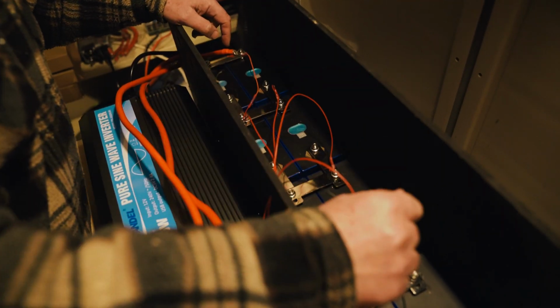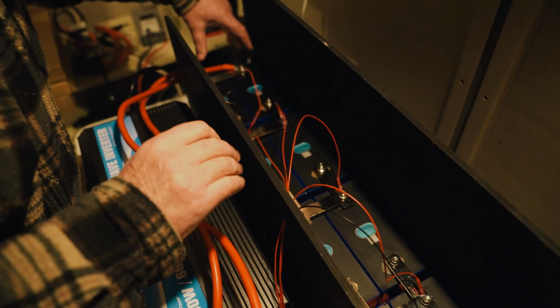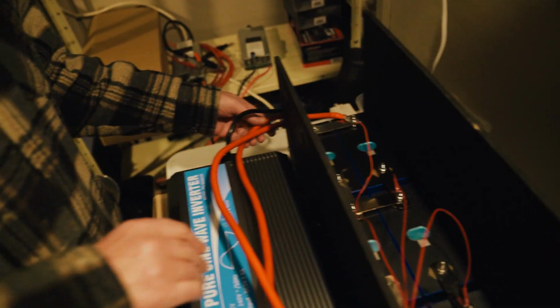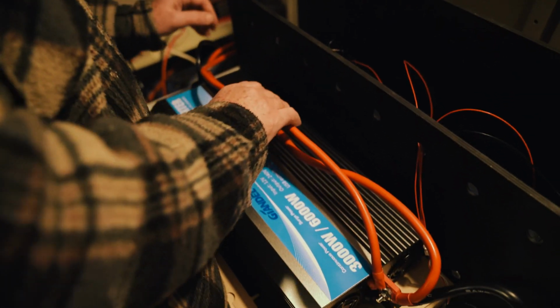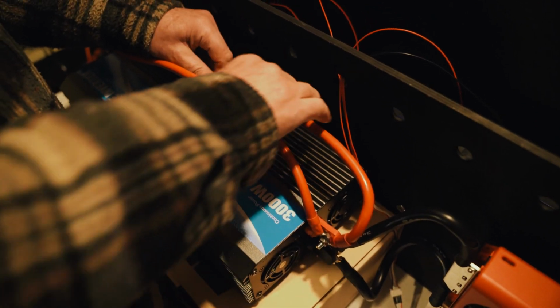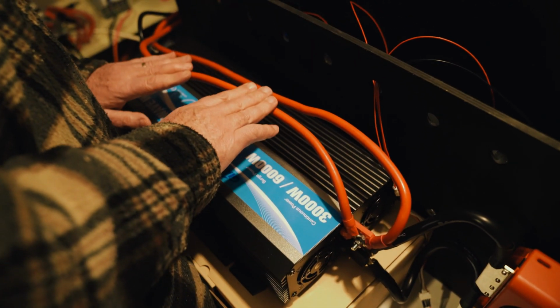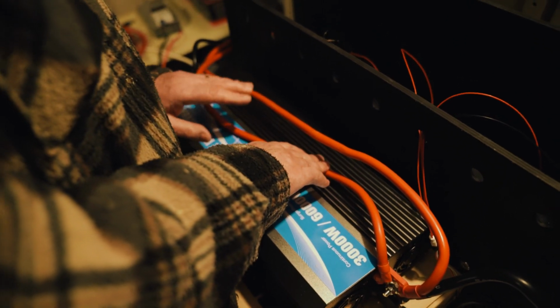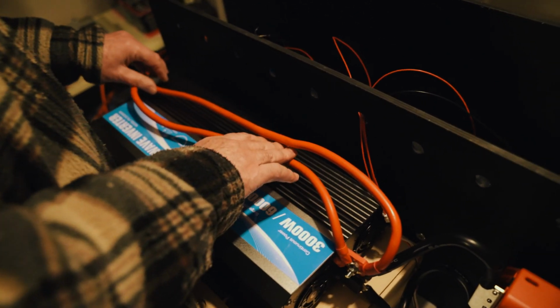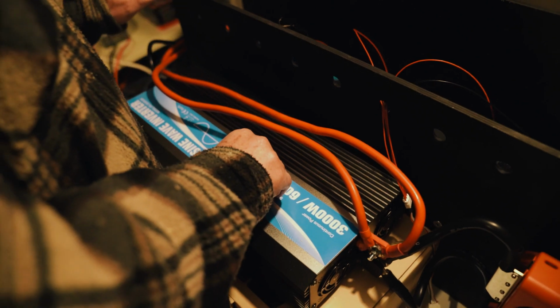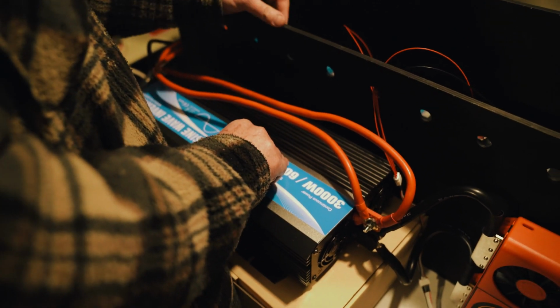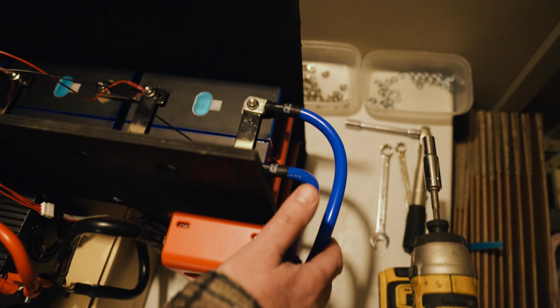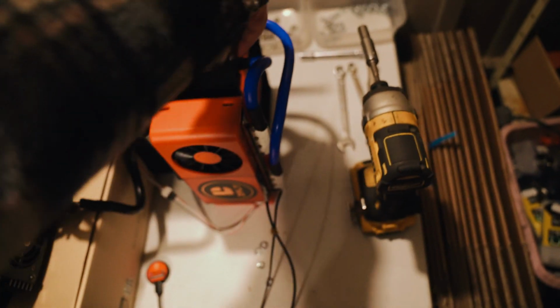This is just so we can monitor temperature across all of the terminals on the cells and the BMS and everything. So we've got the cells all connected up as they need to be, and we've got two 25mm squared cables running to the inverter. We're using 25mm squared for the purpose of this video, which is ample for the total capacity that this inverter and BMS can cope with, so 300 amps. But when it comes to actually building the battery out finally, we're going to put 35mm squared cable there just because we can. On the BMS, it has 4 cables, so 2 going from the battery cells and then 2 to the load and draw.